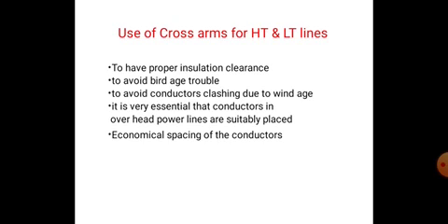And economical spacing of the conductors. We already studied the formula: D = 0.3048 × (0.01 kV + 1.315 d √(S/G)), right?